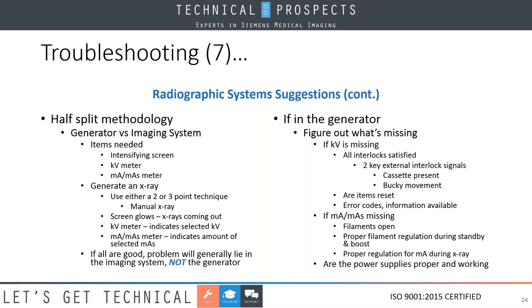Now, if it's in the generator, find out what's missing. Or if it's KV, are all the interlocks satisfied? Are you getting the key external signals, cassette present, bucky movement, etc.? Are all items resetting after the previous exposure? Back in the older days, we had to pull out the cassette and put a new one in and slide that back in. That was a reset function so that we wouldn't double expose the film. Some older systems that have advanced to CR don't have that disabled. So that's a reset function.